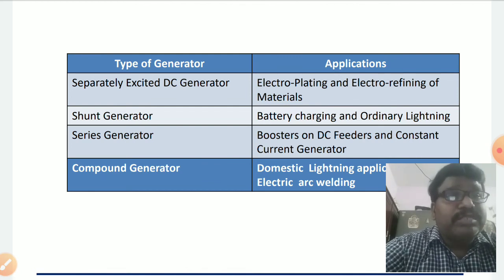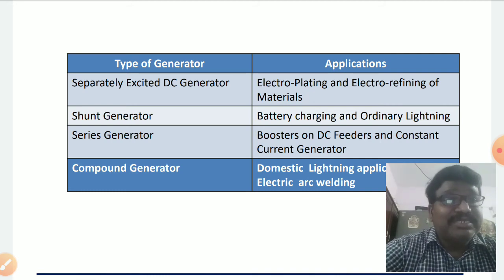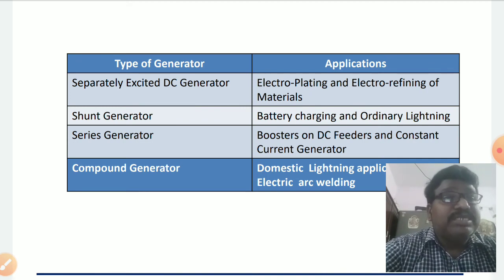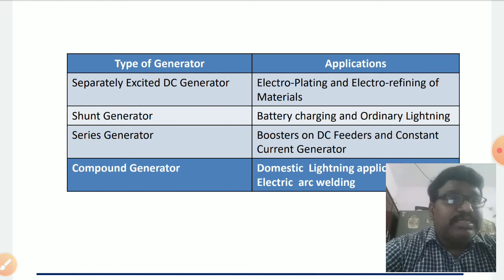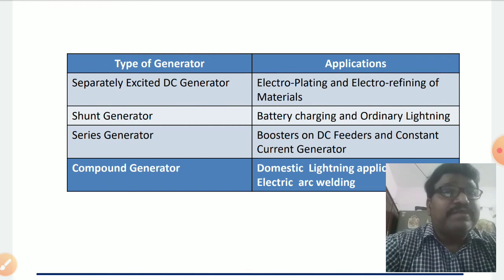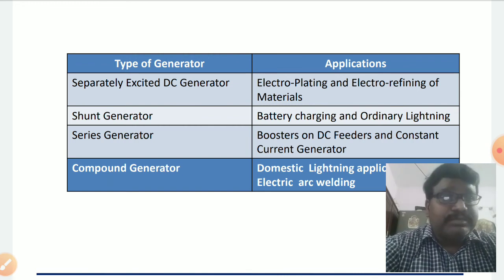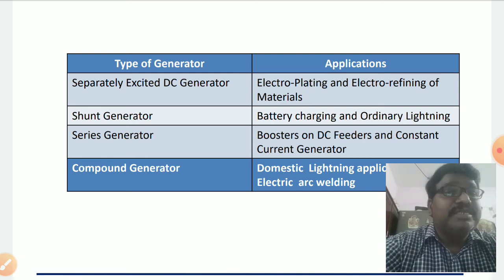With no load, the EMF induced is due to only residual flux, so the amount of flux is very small, and the voltage induced at no-load condition is nearly 10 to 15 percent of the rated voltage. But as the load on the generator is increased, the current flowing in the field winding increases, flux increases, and thereby the voltage increases to its rated value only when there is rated load on the generator.